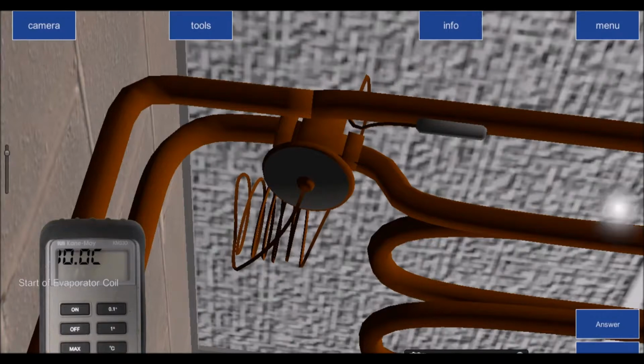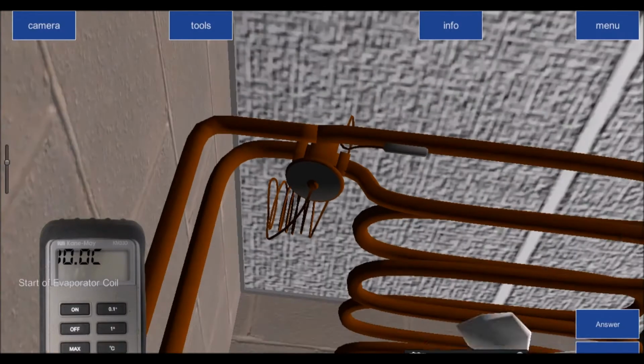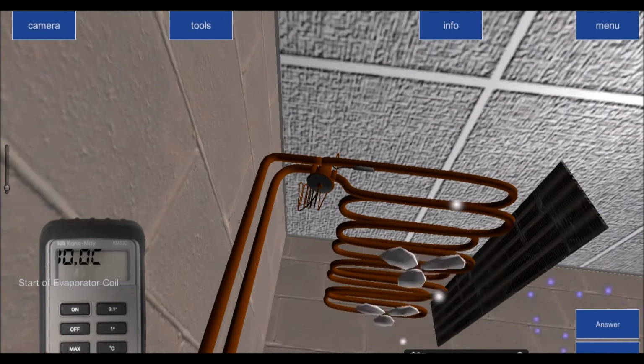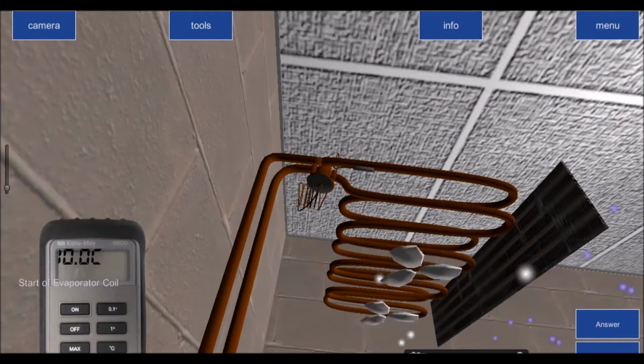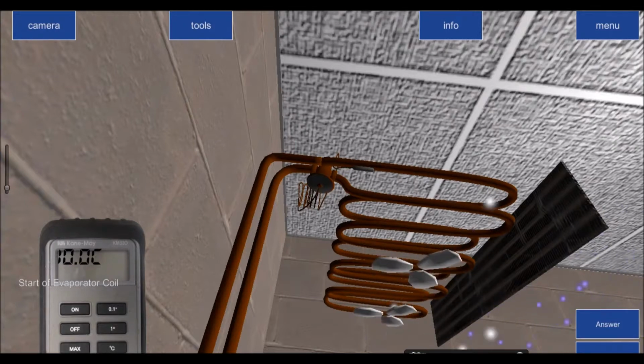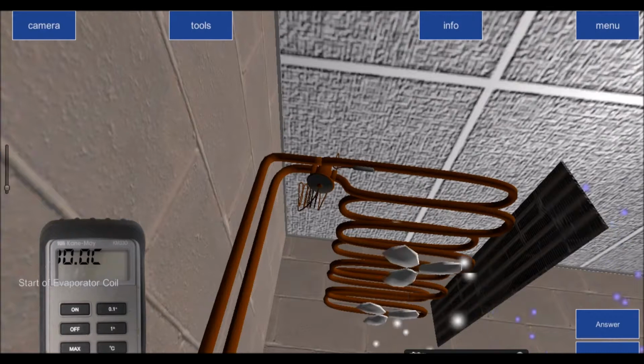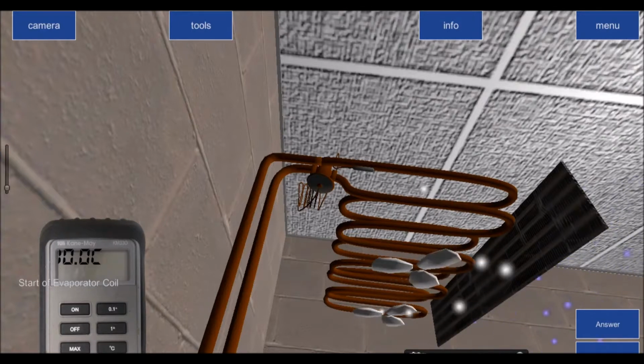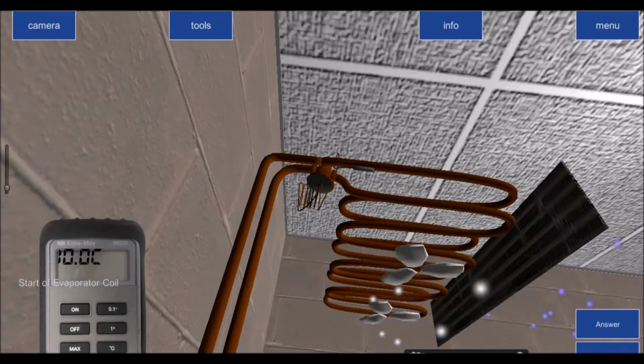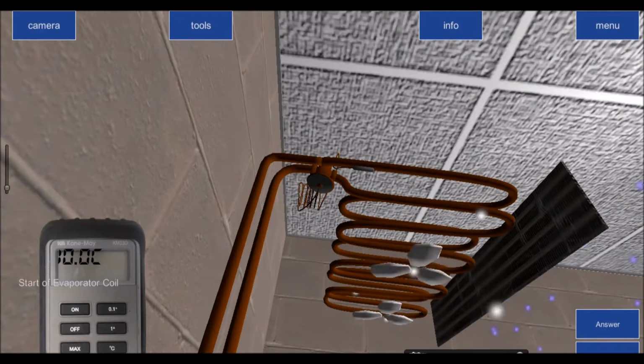Now, I know you're probably saying, well, I'm not going to take the cover off. So in realistic terms, if I was to get my thermometer probe and stick it through the coil and pick up this pipe here, it's the same. I'm going to get the same temperature. If I go along and follow that pipe and pick up this pipe here from the front, it's going to be the same temperature. And if I keep going along and get to this pipe here, it's going to be the same temperature. It's only when I get to this top section here.